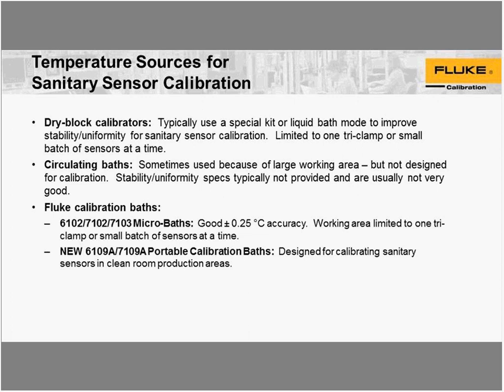The difference between the calibration bath and a dry block calibrator is that the calibration bath uses fluid, which is a lot more flexible for measuring sensors of different geometries. So at Fluke, there are two categories of calibration baths now. There is the traditional micro bath category. It's been around for years, has been a very popular product. They have an accuracy range of about 0.25 degrees, and are very small. The working area is small enough that one tri-clamp sensor is all that you can fit into one.